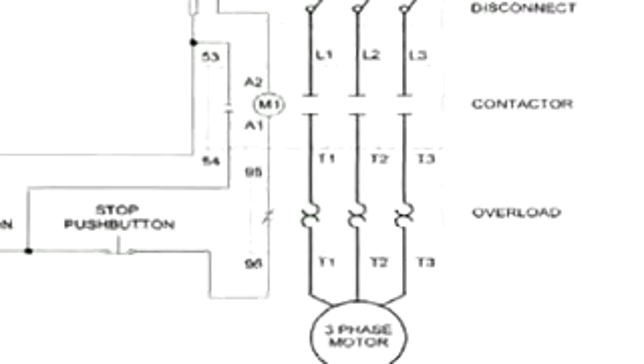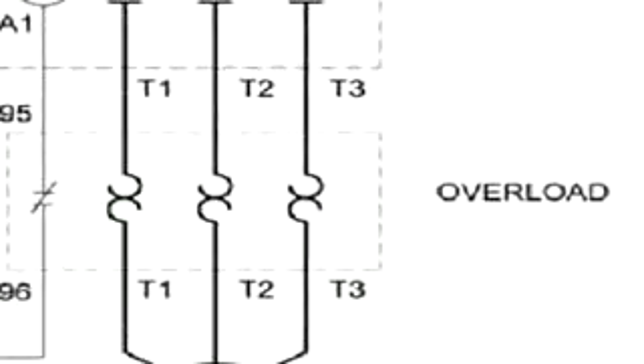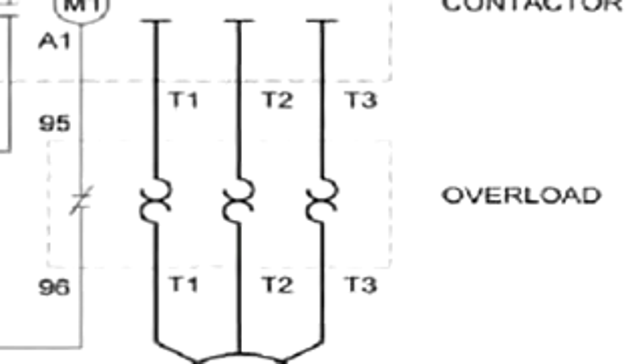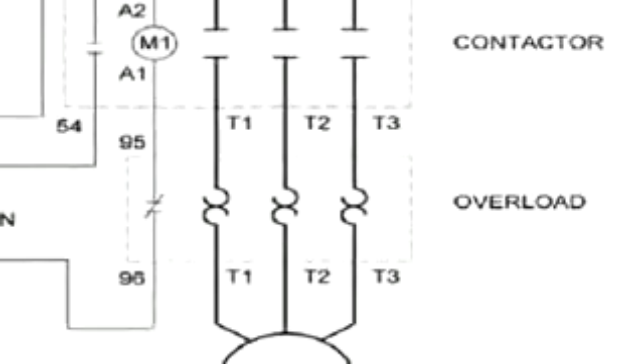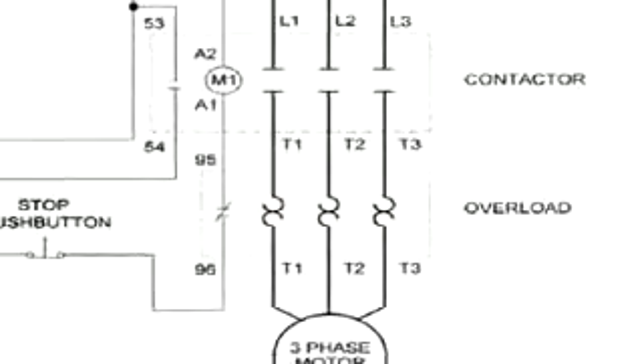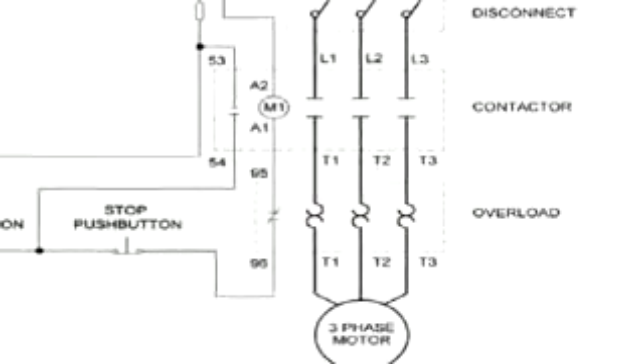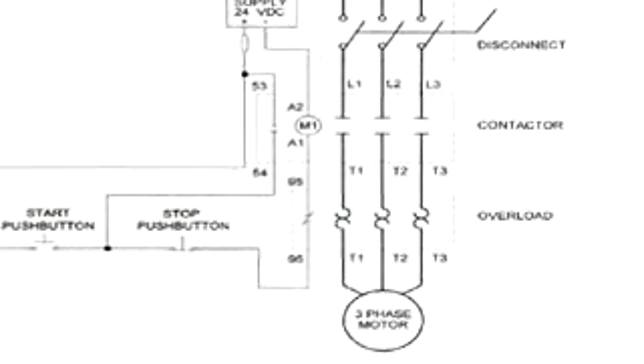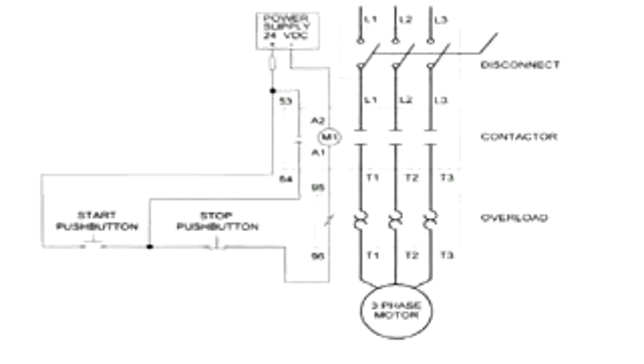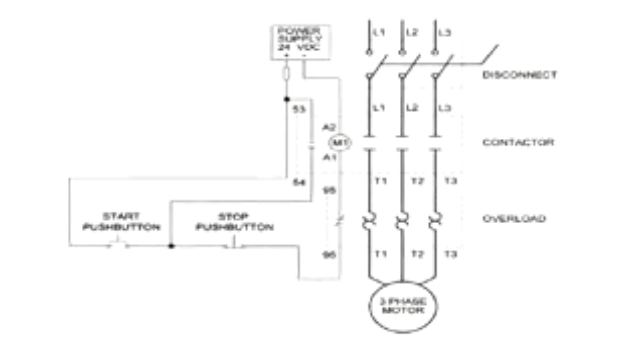You still have that list, right? Let's keep moving backwards. Let's check the overload. Most overloads have indicators that indicate when tripped. If the overload is tripped, do not immediately reset. Investigate the cause of the overload. Most overloads are caused by mechanical overload. If no mechanical cause can be found, megger the motor. If the overloads are not tripped, check resistance across each overload. There should be no resistance from top to bottom.